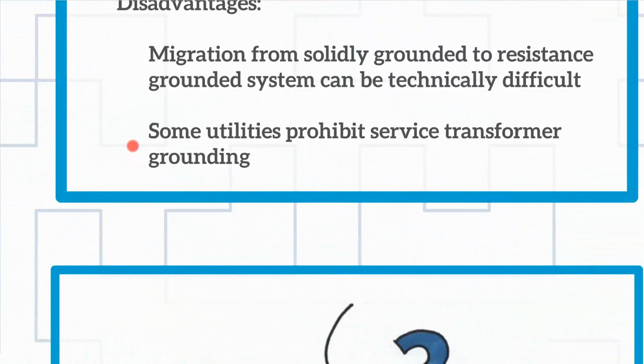So they want very high amps to quickly blow fuses on the primary. This is the utility's reason for forcing it. And what I do is say, okay, I understand what you want, but in the meantime, at that voltage level, anytime they get a ground fault, which is 90% of the faults, down in the system for the end user, it costs him megabucks with cables and other issues. I want a high resistance or low resistance ground in your transformer, and we'll put protection in there. And so for all the faults down in their system, we're going to limit it to 400 amps, and that's going to protect your transformer.